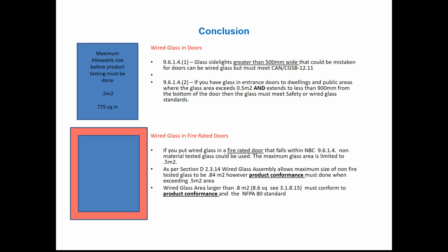So once again, this is just a brief overview of wire glass. What I would look at is the size of the wire glass. I would look to see if the size exceeds the limit and if it has to be tested in accordance with NFPA 80. So you should drill down a little bit harder when you see wire glass being used and ask yourself some questions: A, is it impact? Is the size exceeded? And does it have to be labeled? I don't know if that helps you out, but at least it gives you some food for thought.